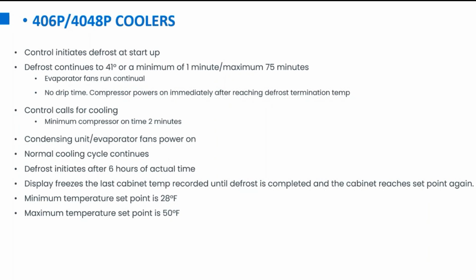That 35 degrees is going to remain on your display until that defrost has satisfied and the next cooling cycle has also satisfied. So in normal operation, nobody would ever even notice that it happened. But if you're a tech out there servicing the unit, obviously you have it powered off, you're working on it, the cabinet gets up to room temperature, and then you finish your work, you get the unit power back on, your compressor kicks on, begins to cool.